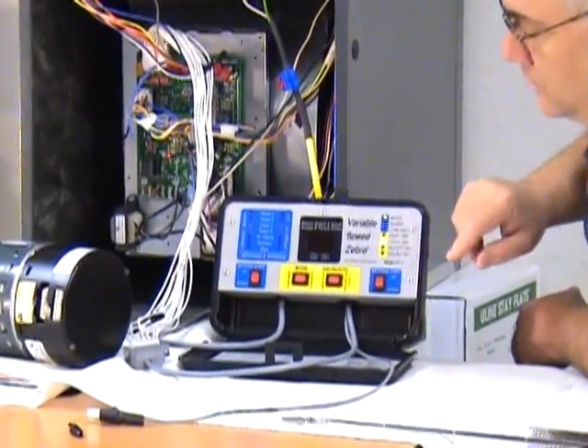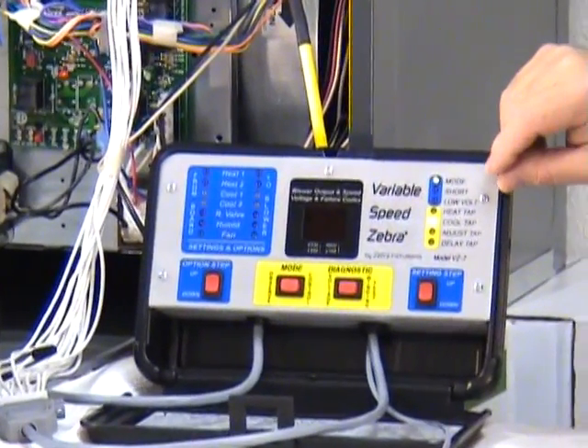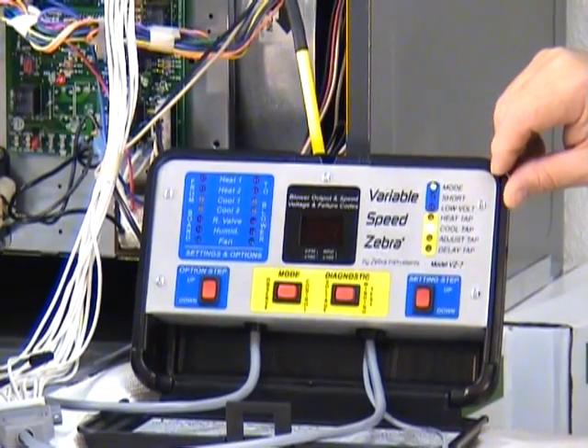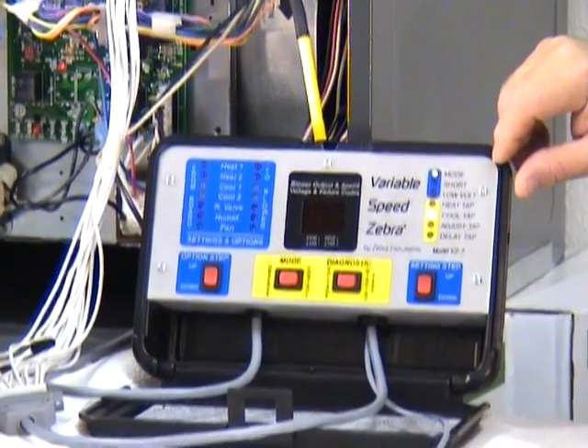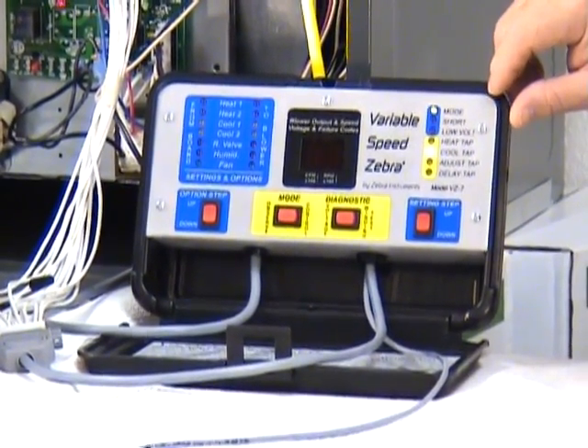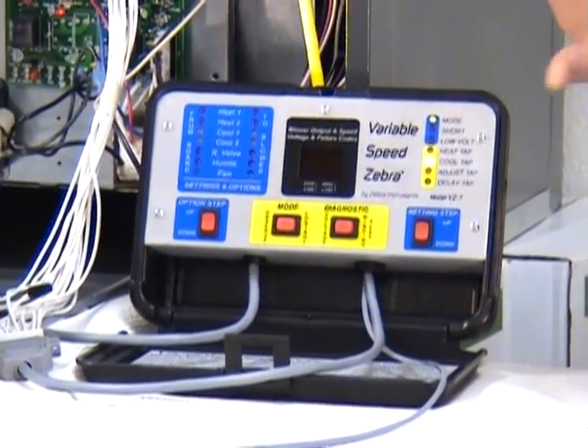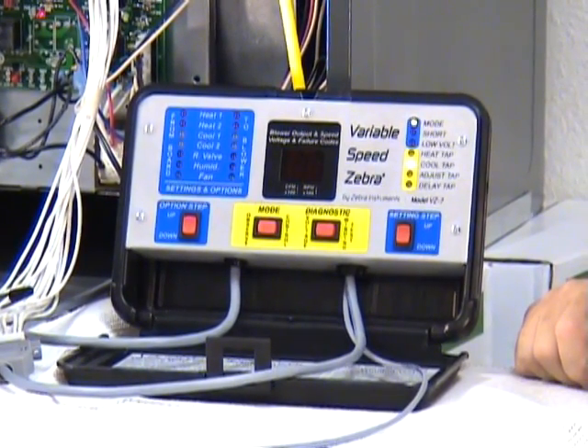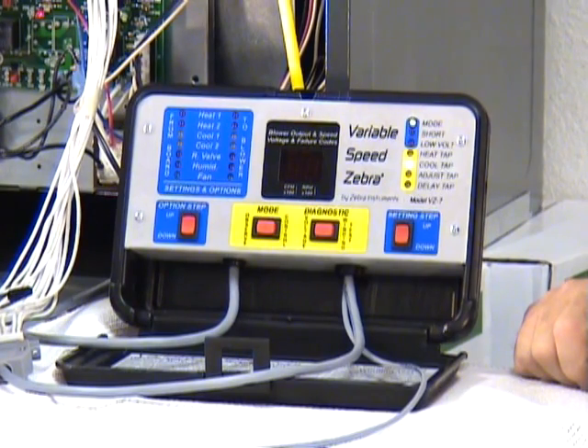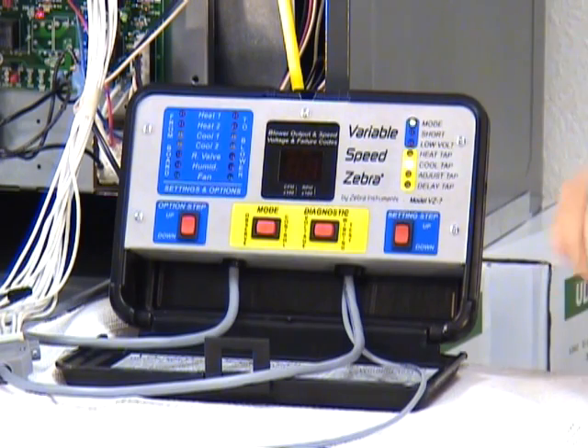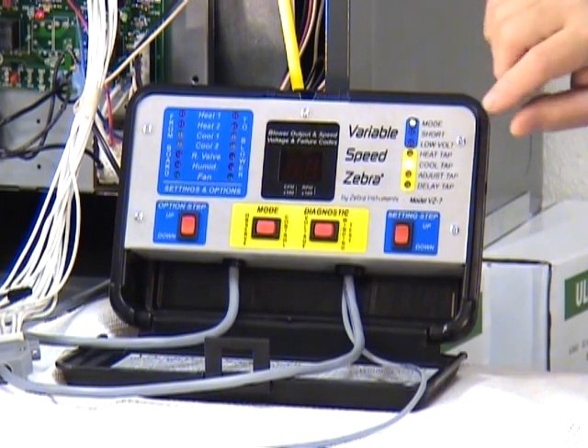You're going to have to listen to the theory section of this DVD to understand what those taps do. I'm not going to try to go into what they do now, but different manufacturers even have different meanings for them. Whenever you're doing an installation for the very first time, or service where you have a motor that's running but there's a speed issue, or it's pushing the condensate off the coil because it's running too fast, or the customer claims it's running too slow, one of the first things you should do is check those settings.